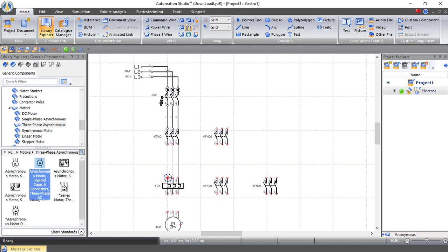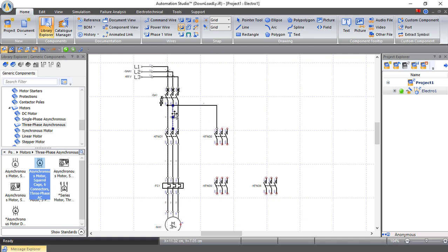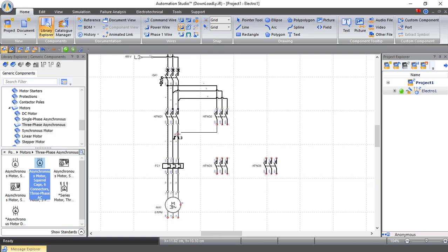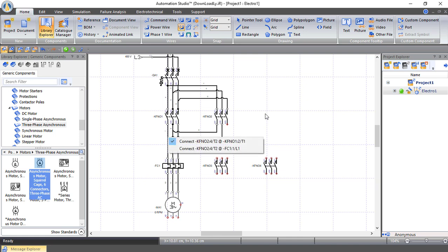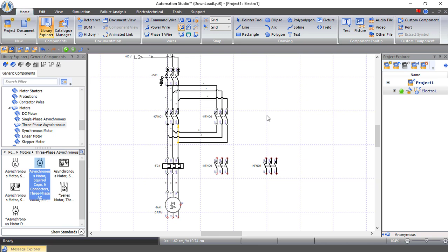From Power Wires, let's connect our power circuit. This is the main circuit breaker. I want this contactor to be forward direction and this one to control the reverse direction. I will choose a power wire as a single wire and connect it to the second contactor, the reverse contactor. From the end here, I will make an interchanging in cables — this one connected to the second wire and this second connected to the first wire — to interchange the power source, which will make the motor rotate in reverse.